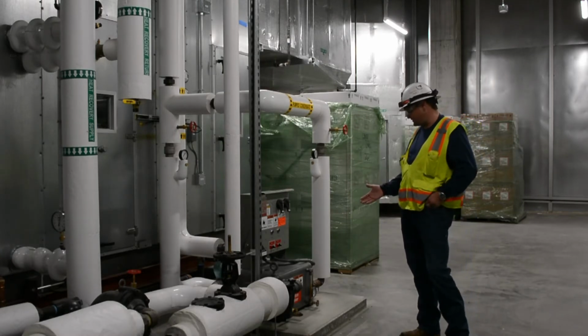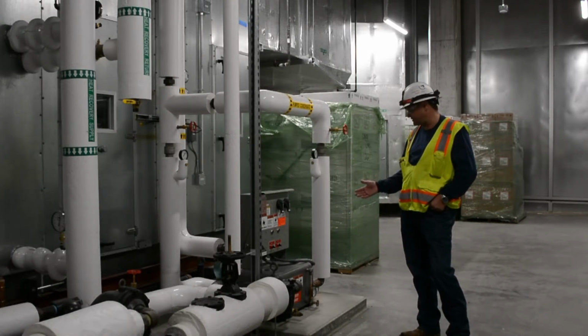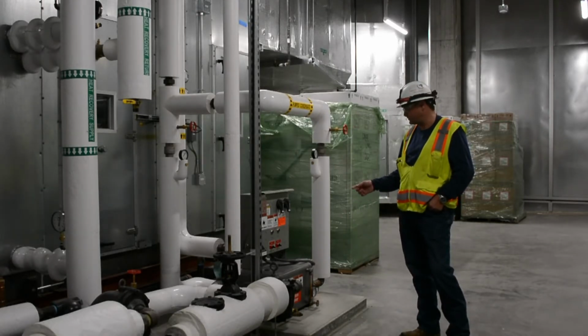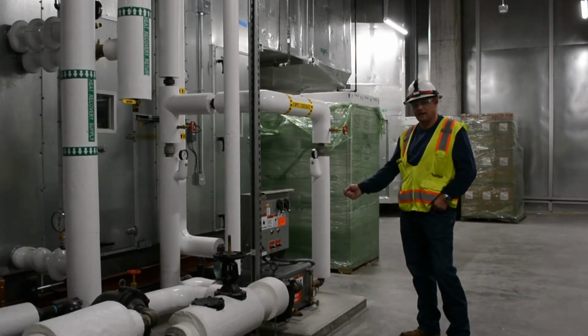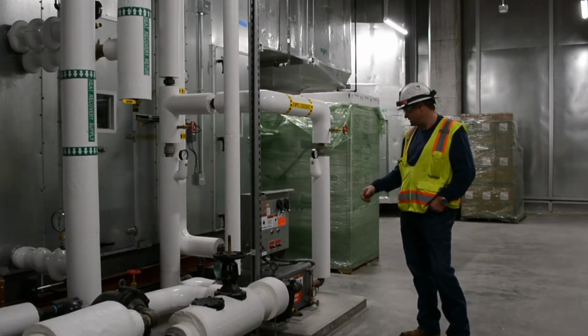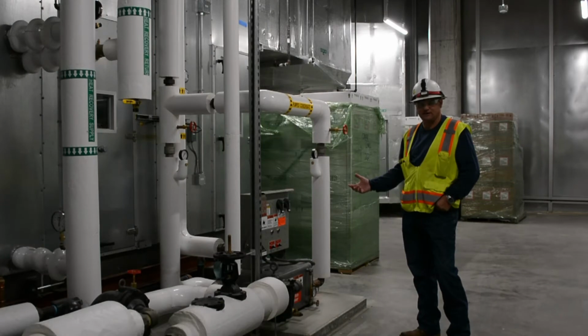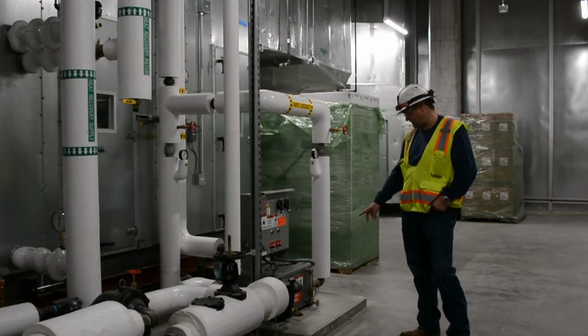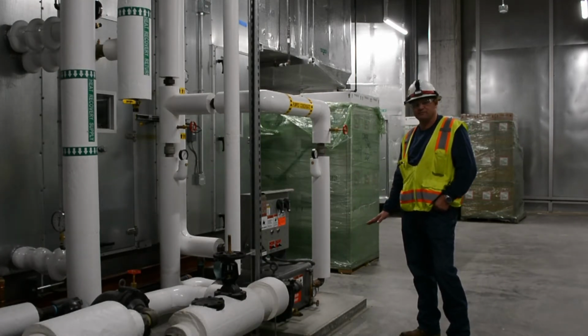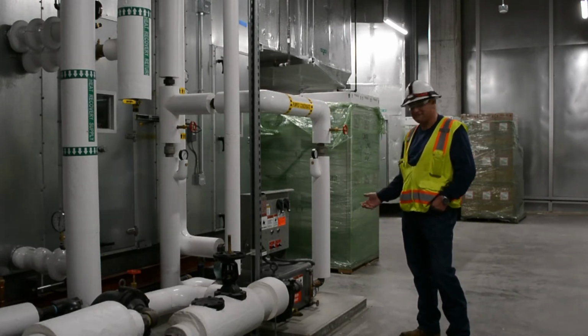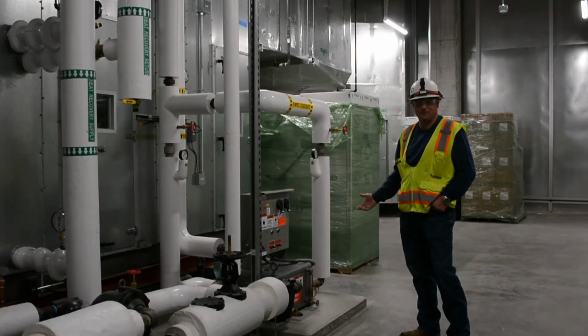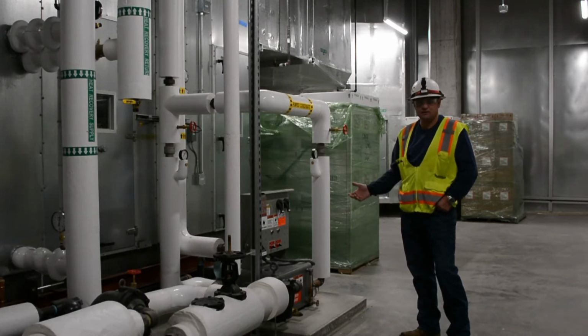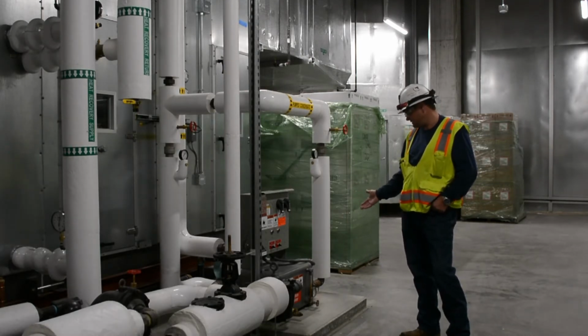This condensate receiver does have routine maintenance required. You want to verify that the operation of the pumps is stable. You can test these by putting them in the hand mode and operating the pump. Just look for any unusual noises, sounds, vibrations, and ensure that the sight glass actually lowers whenever the pump is in operation so that you can tell that the pump is working. If it is not working, you'll have to disassemble the pump and see if there's any debris or anything clogging it, or if the pump itself has been compromised and is broken.